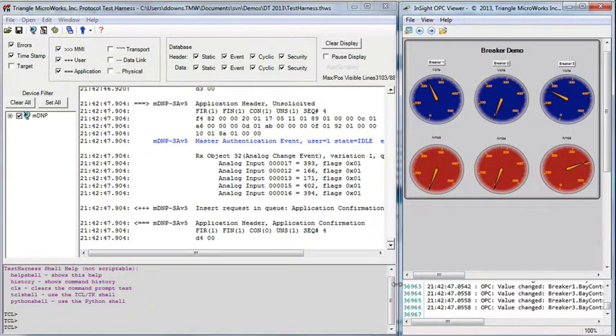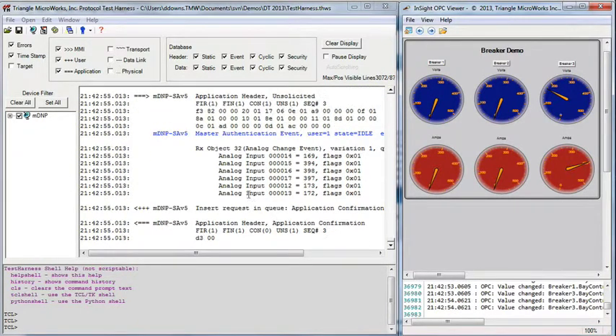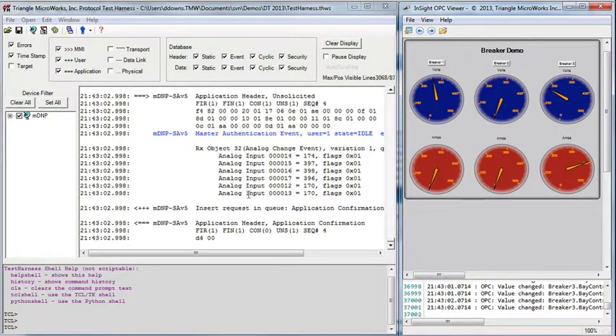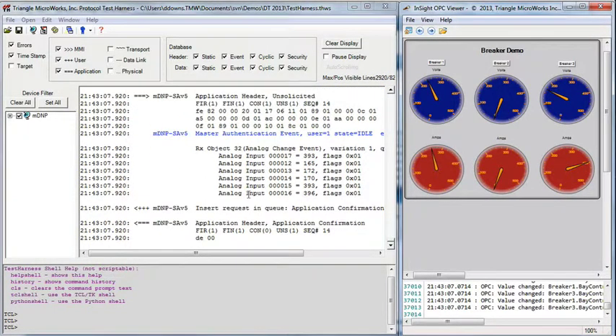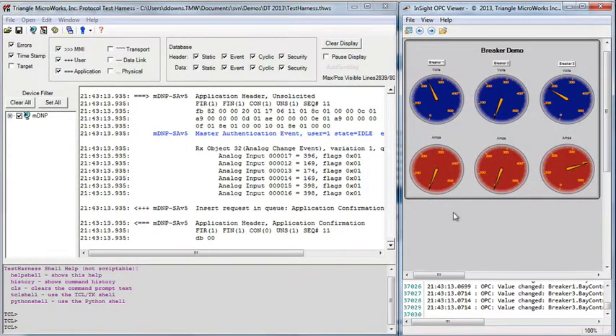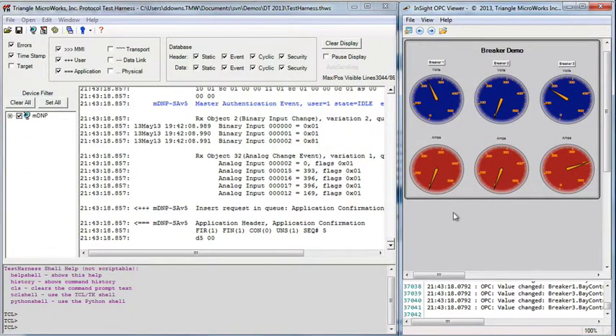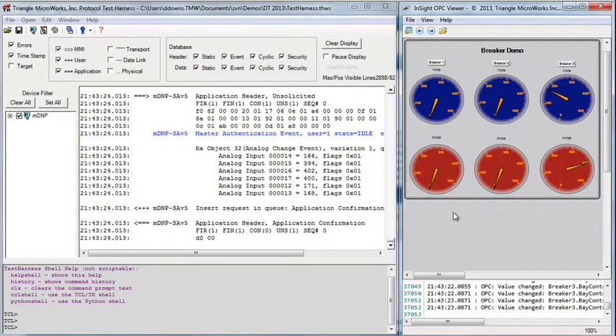Back on the host PC, we have the SCADA Data Gateway running along with the Insight OPC viewer. In the test harness, the protocol analyzer log is showing communications from the SCADA Data Gateway. The blue lines indicate secure authentication events, so we can see Secure Authentication running as values are updated. On the right side, the OPC XML DA client shows the phase A current for each of the three breakers, changing as the gateway reports new values.